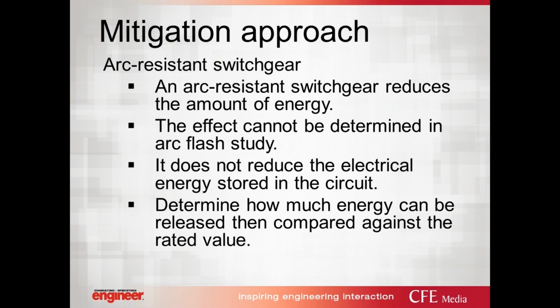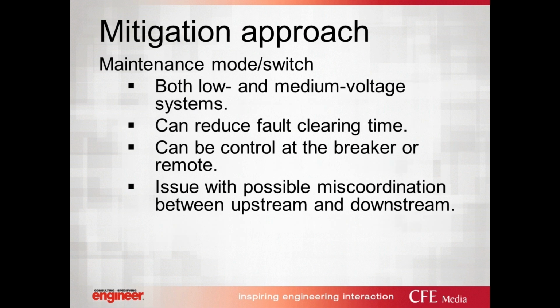Something I need to point out that arc resistant switchgear reduces the amount of energy. The effect cannot be determined in an arc flash energy study, you cannot determine this impact. You should know that the arc resistant switchgear does not reduce the electrical energy stored in the circuit. What it does, it gives you what the capability would be, what you need to do, determine the energy based on your system, compare it against the rated value for this type of switchgear. Therefore, the point I want to make here, it does not reduce the electrical energy stored in the circuit. You need to compare it against the rating that the manufacturer provided to you and based on the energy that you calculate in your system.